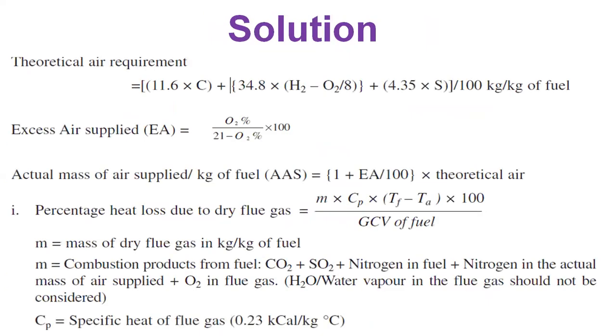First, we calculate the theoretical air requirement using the formula: 11.6 × C + 34.8 × (H₂ − O/8) + 4.35 × S, divided by 100, in kg per kg of fuel. The excess air supplied is given by: (% O₂ / (21 − % O₂)) × 100. The actual mass of air supplied per kg of fuel is: (1 + excess air/100) × theoretical air.